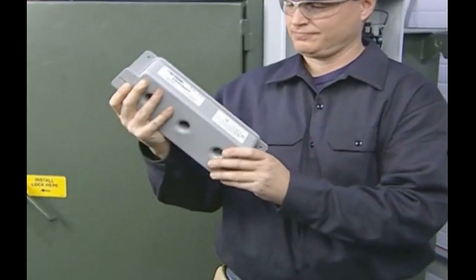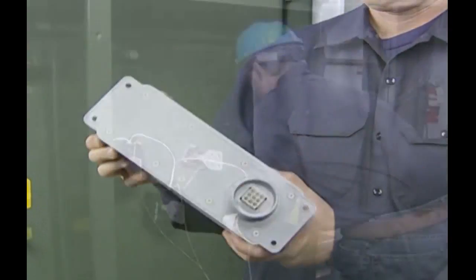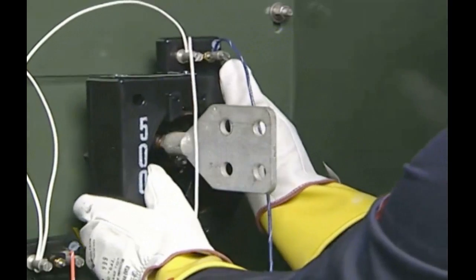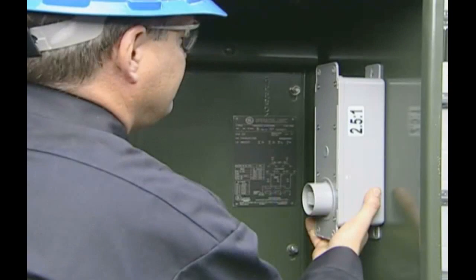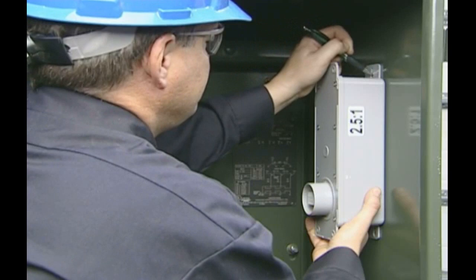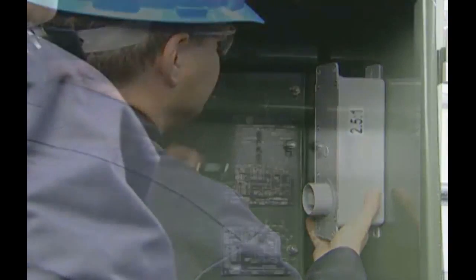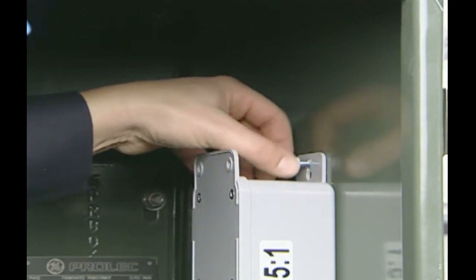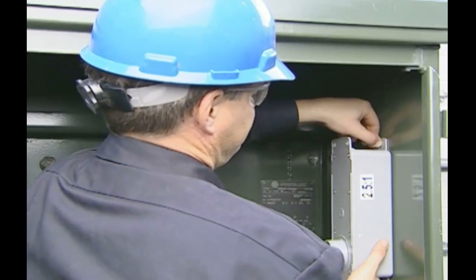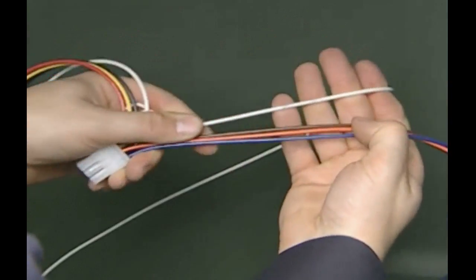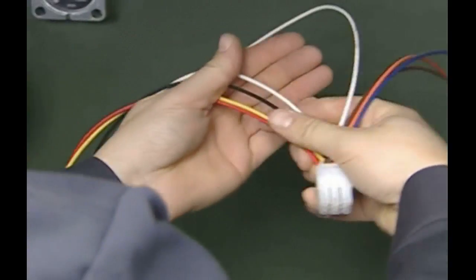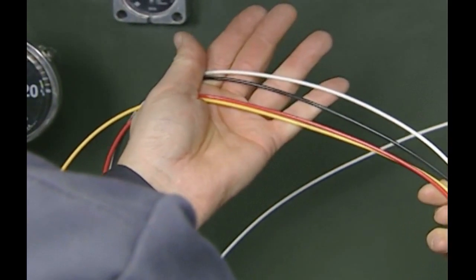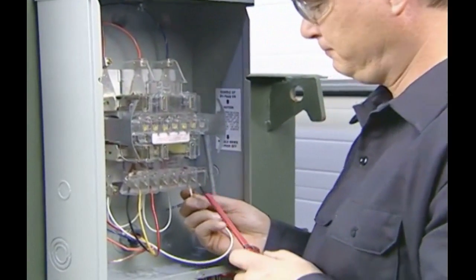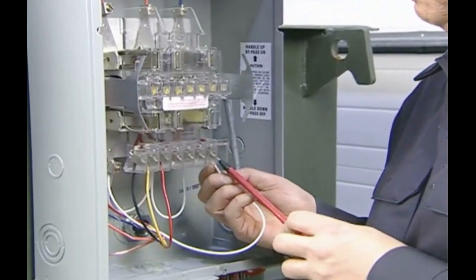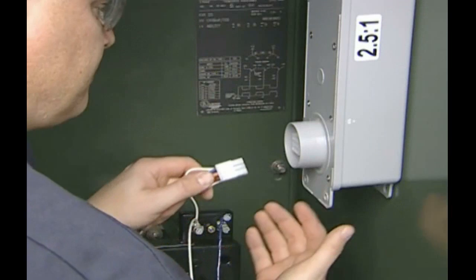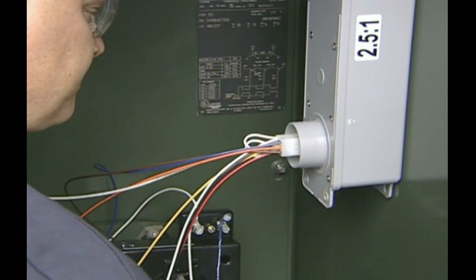Installing a VT pack is much quicker and easier and requires a minimal tool set. First, install current transformers, or CTs, on the transformer's main bushings. Hold the VT pack where it will be located inside the transformer housing, and mark where you intend to drill one hole. Drill the hole and bolt the VT pack inside the transformer housing. In connecting the wiring harness, there will be a maximum of only 4 connections inside the transformer cabinet, and a maximum of 4 connections inside the socket cabinet. After connecting the harness within the cabinet, feed the other wires into the socket cabinet through the bushing and properly connect the wires. Plug the wiring harness into the VT pack and then plug in the meter. You're done.